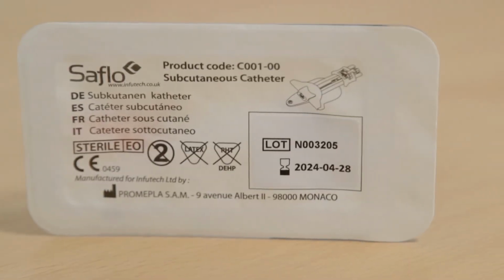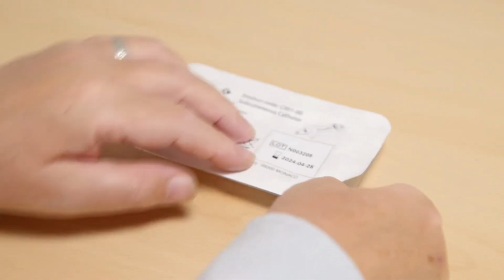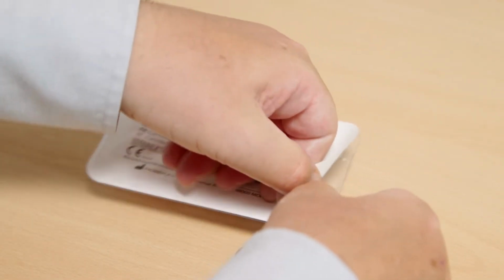Before use, it is important to take note of the device lot number, which is clearly printed on the label of the device itself and on the box in which the device is delivered. This is important to make sure it is possible for the manufacturer to investigate any problems which may have been reported with this batch. Firstly, peel back the label and remove the device from the packaging.